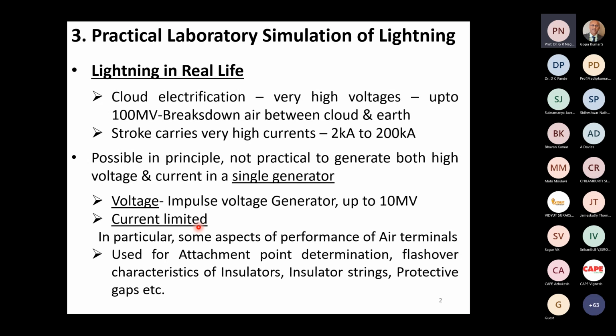In particular, some aspects of performance of air terminals, used for attachment point determination, flashover characteristics of insulators, insulator strings, protective gaps etc. can be studied. Now, these air terminals are not the Franklin rods or ESE terminals. What I am saying is, if you think of an aircraft, which is a very odd-shaped body compared to a normal building, where does the lightning most probably hit? For deciding such attachment points, we use these lightning test facilities, and either full-scale models of the aircraft or scaled models are also used quite often.